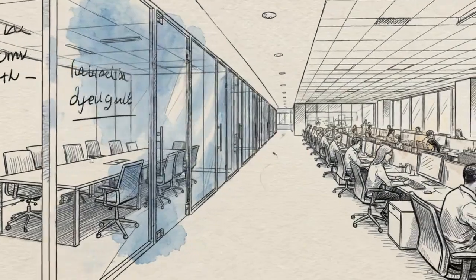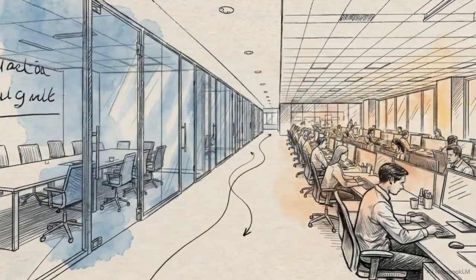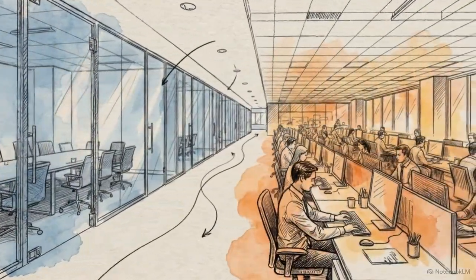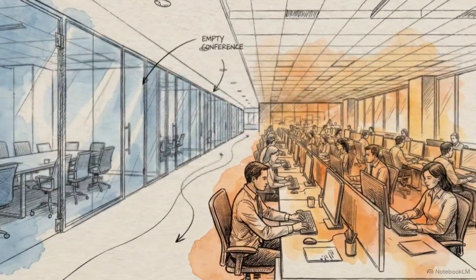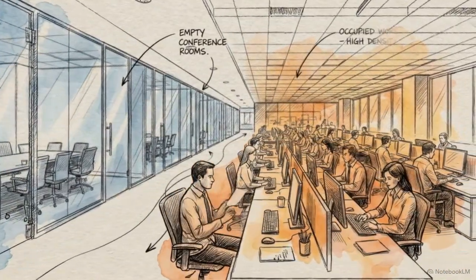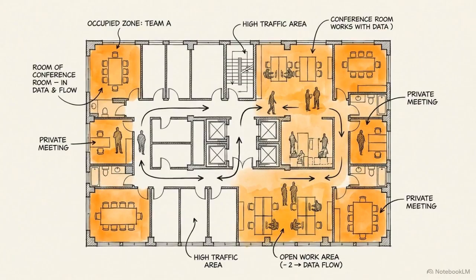Relying on a fixed schedule is a building's biggest energy vulnerability. Occupancy is uneven. Meeting rooms sit empty while open-plan desks are packed. The ultimate efficiency multiplier is occupancy-based control. This strategy shifts the system from anticipating human presence to actively reacting to it. Detecting human presence requires specific sensors, each with blind spots.